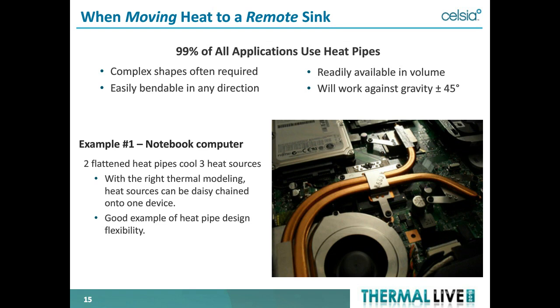When moving heat to a remote heat sink — probably 99% of all applications from a volume standpoint, most being computing applications — complex shapes are often required. Heat pipes can be bent relatively easily, just like copper tubing, and they're available in huge manufacturing volumes — many millions per month. They work against gravity reasonably well: for a laptop application, up to about a 45-degree angle. In the notebook example shown, two flattened heat pipes cool three heat sources by daisy-chaining to move heat from multiple heat sources — fairly common.